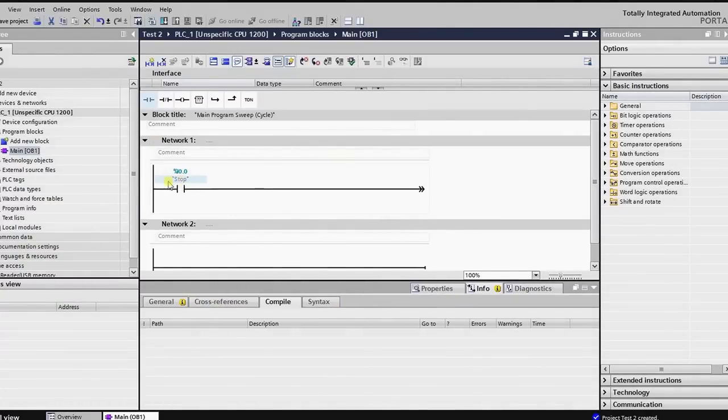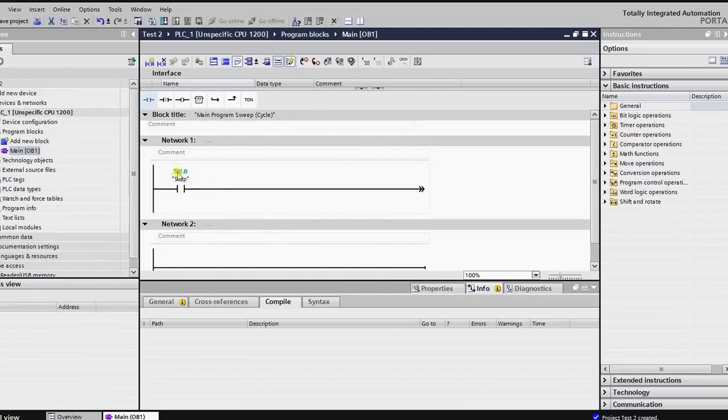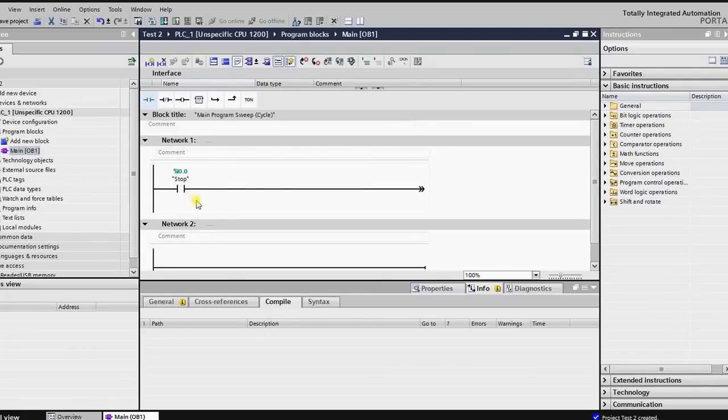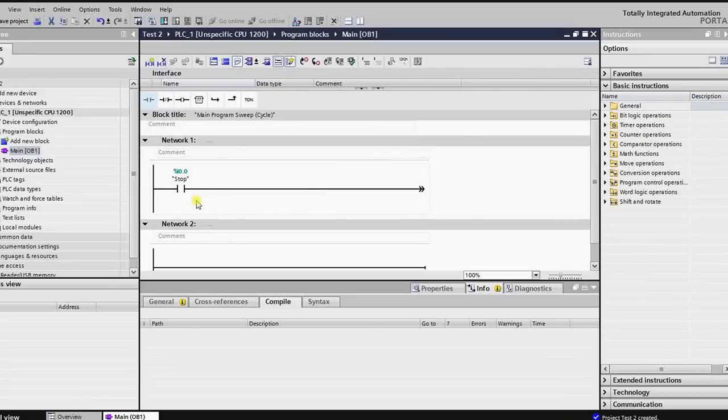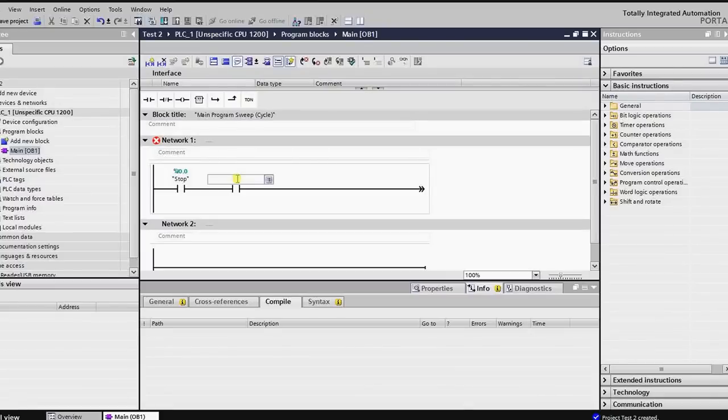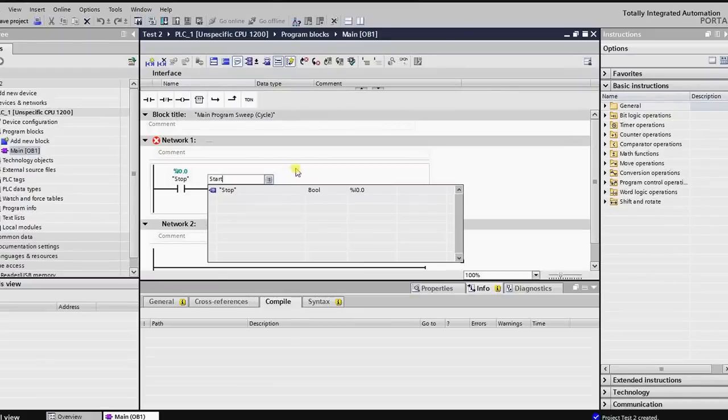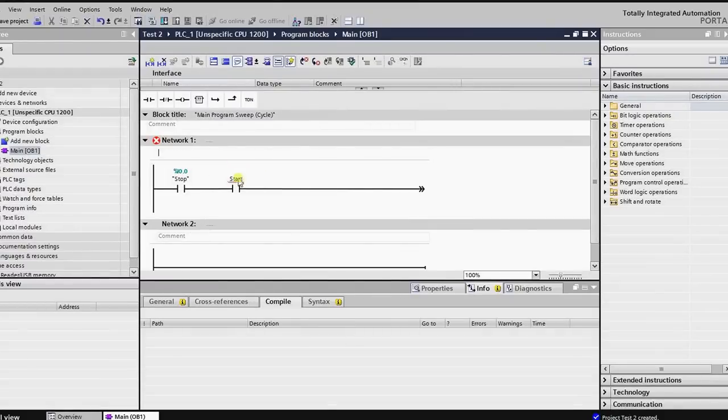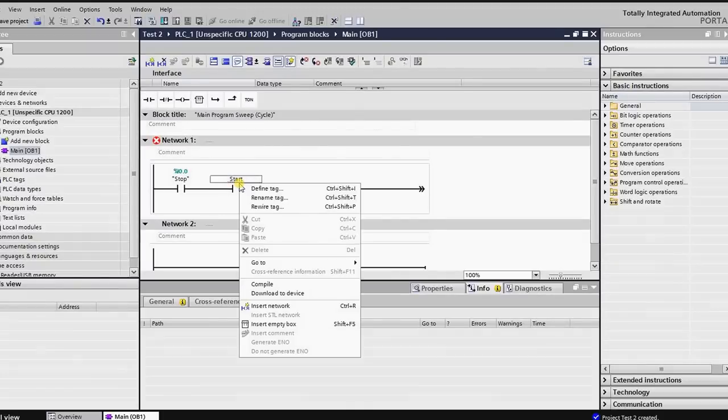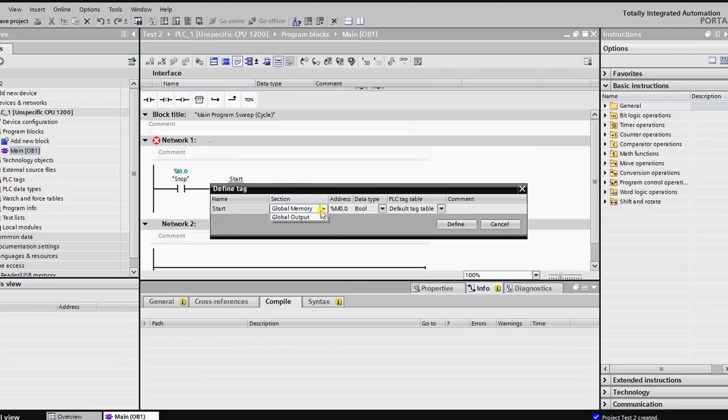You'll notice that the stop is now in quotation marks. It is not underlined in red, which means it is correctly done, and that it now says %I0.0, and that means that on your PLC, your power will go through your stop button, and on the other side of the stop button, it'll go to input dot zero, or the zero at the top of the PLC. And so you just want to click on the right of whatever you last did, and click Add Another Input, and this will be our Start button, and any time you start to type anything, if there's similar names, you can actually click down here, and it'll assign them to the same thing. So you can see again, as we typed in Start, it's underlined in red, because it wants us to define the tag. So again, your Start is another input.